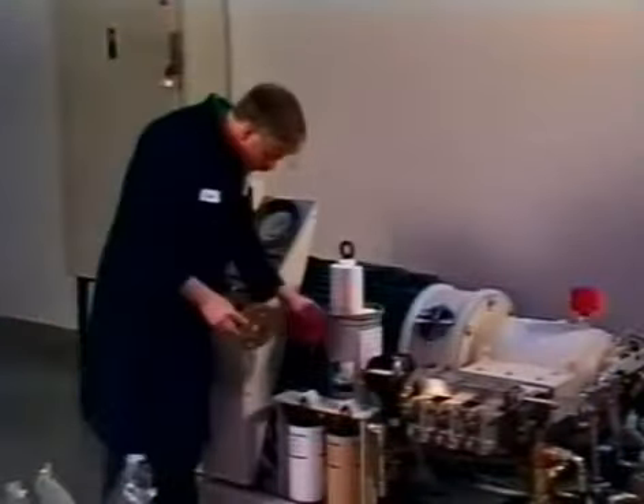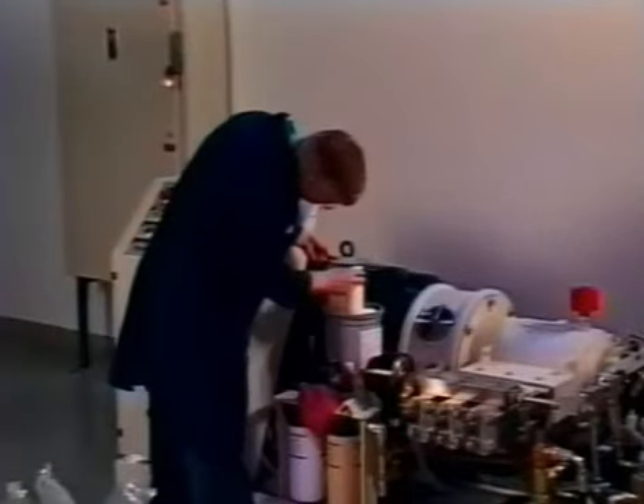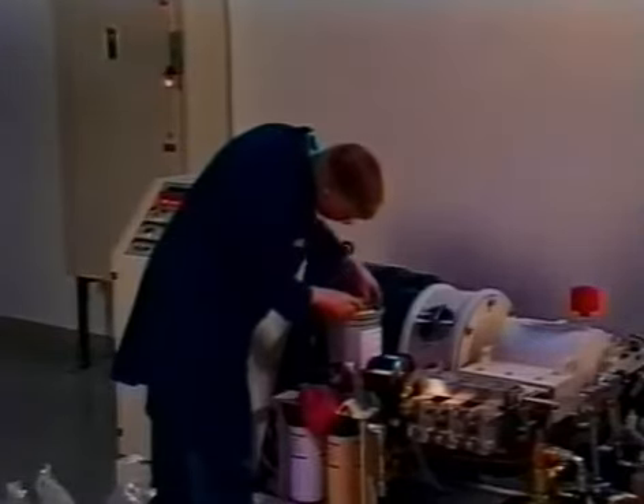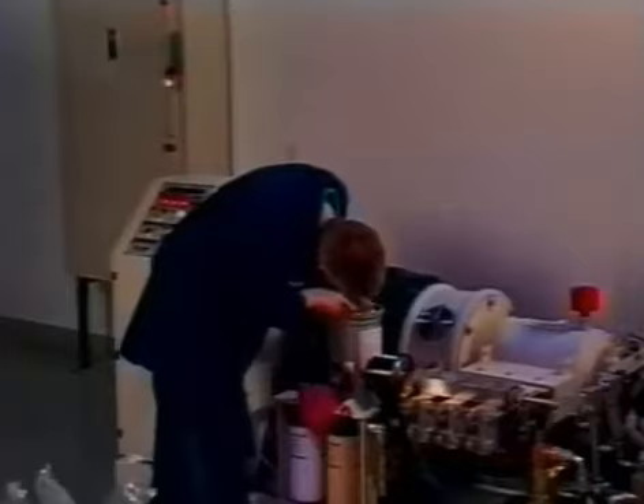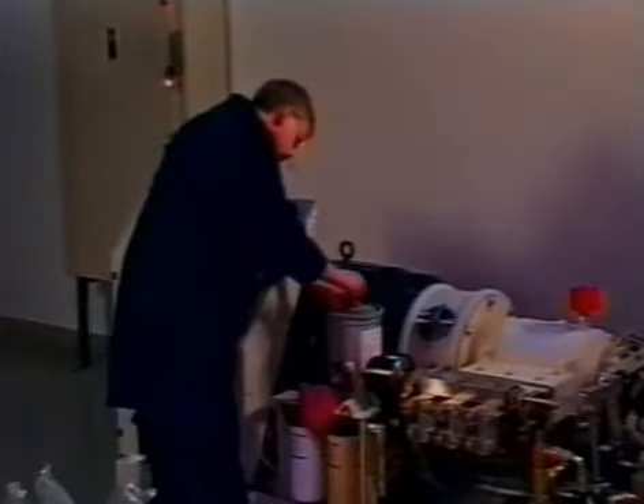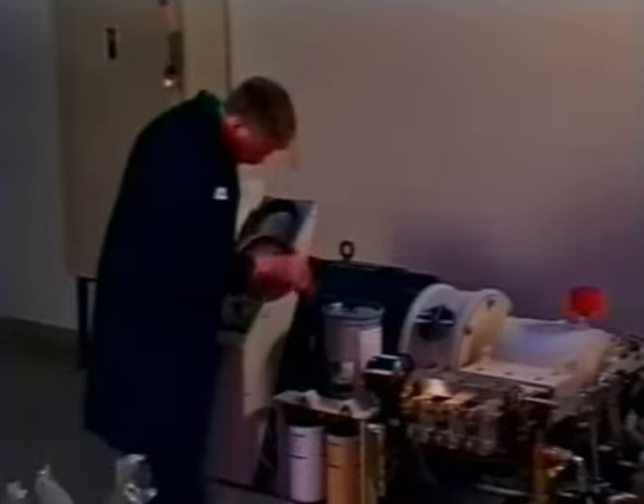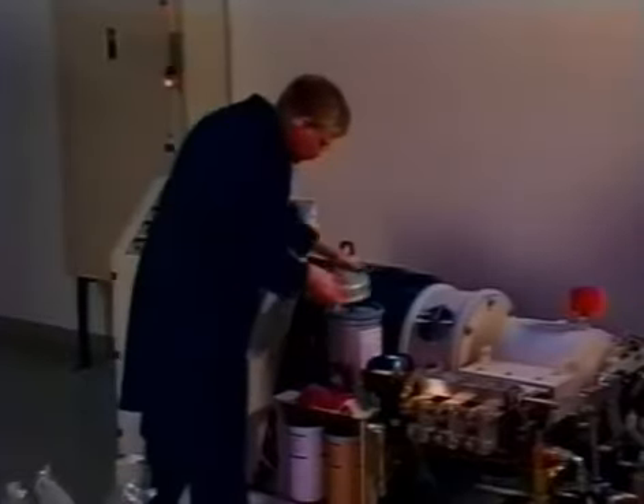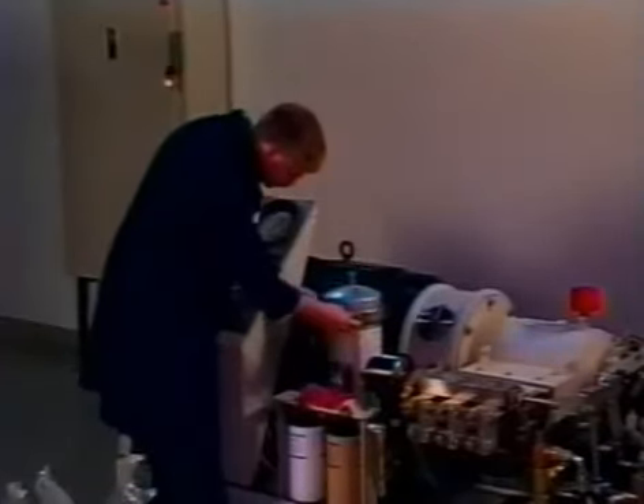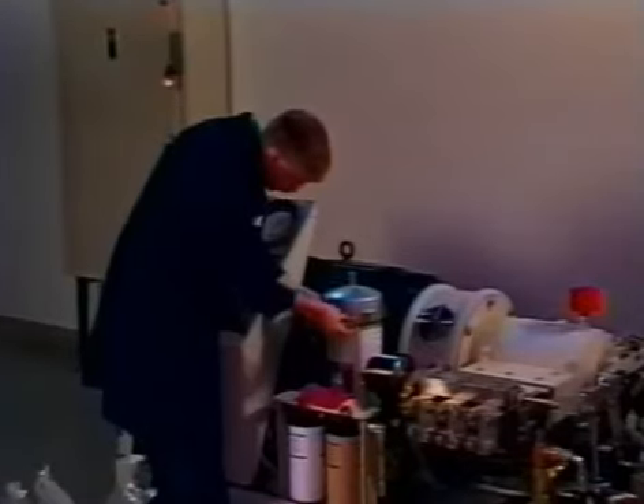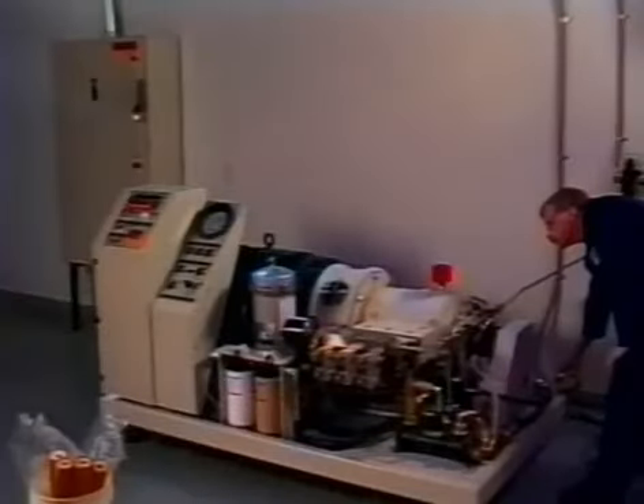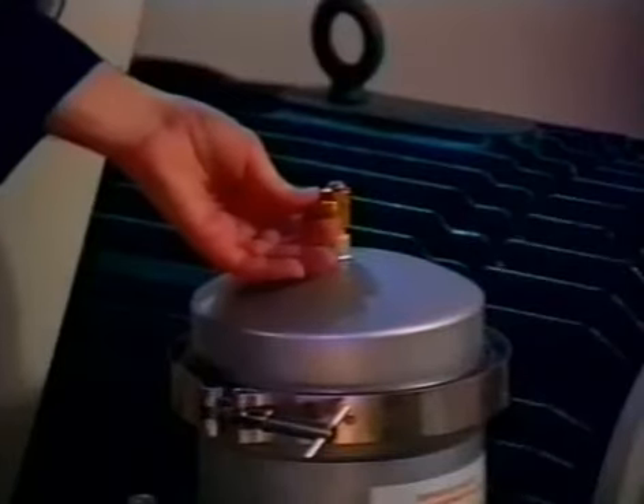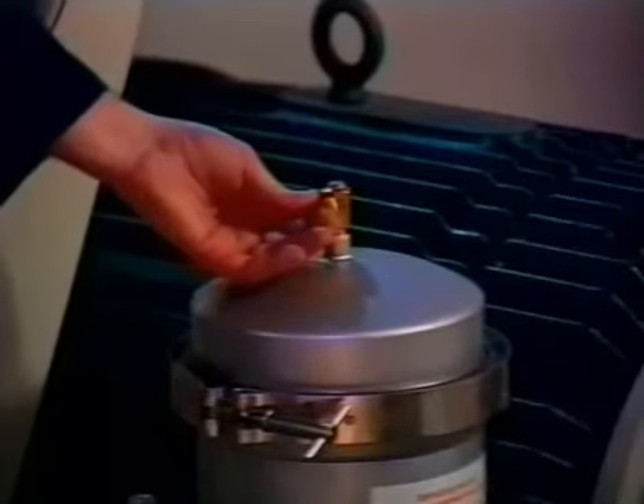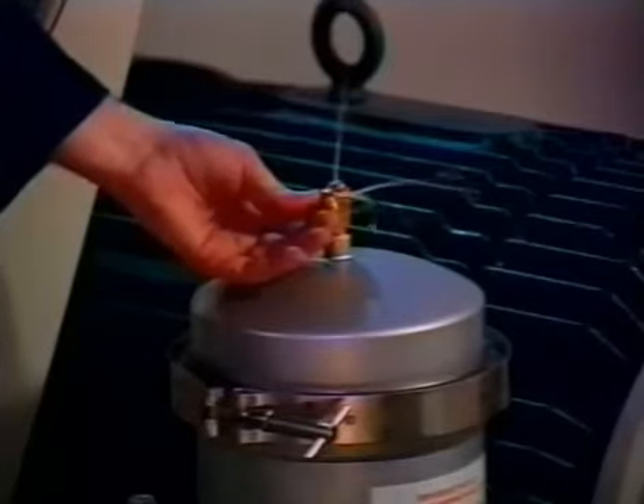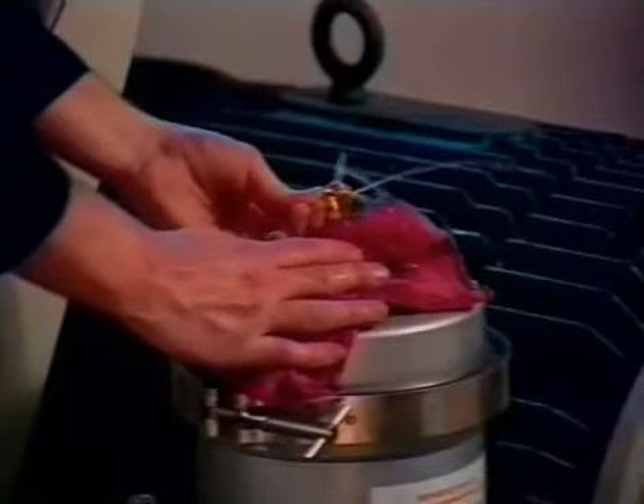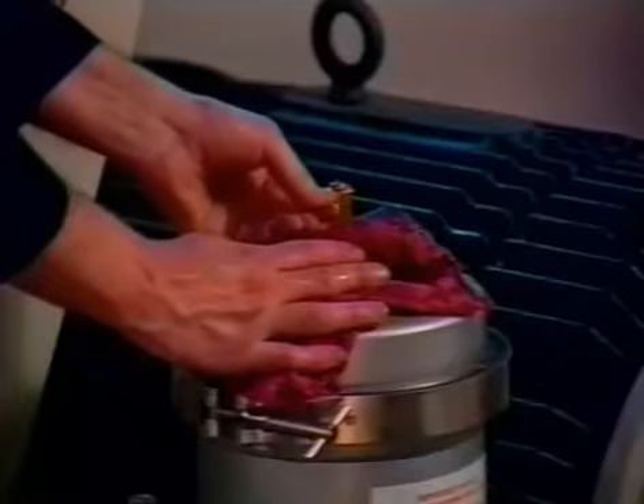Install the filter plate and thread the handle into position. To prevent unfiltered water from flowing past the filters, be sure the filter plate is pressed firmly and evenly against all the filters. Replace the top and close the vent. Open the inlet water valve. Now, to vent the air from the filter housing, reopen the vent until a solid stream of water is noted. Restart the Husky pump using the startup procedure.